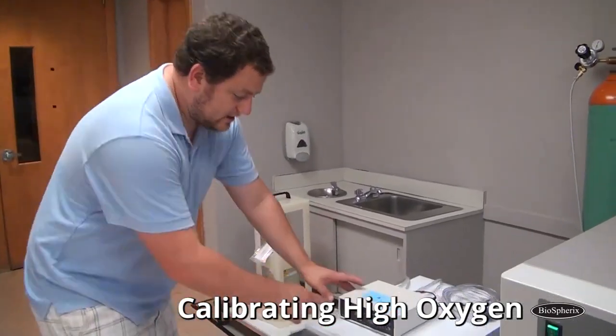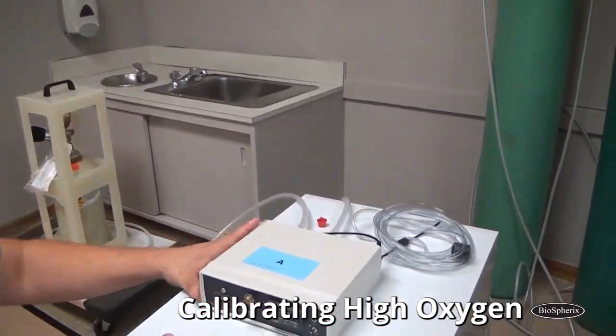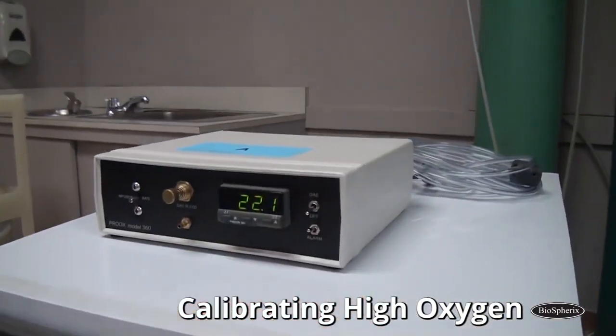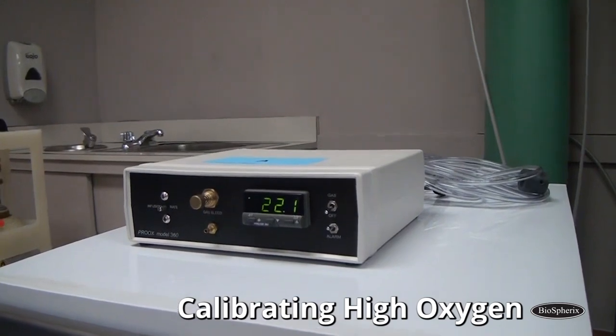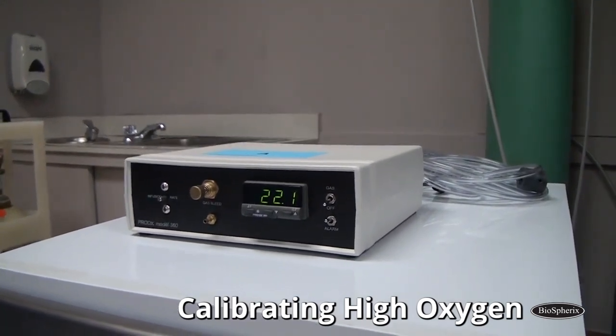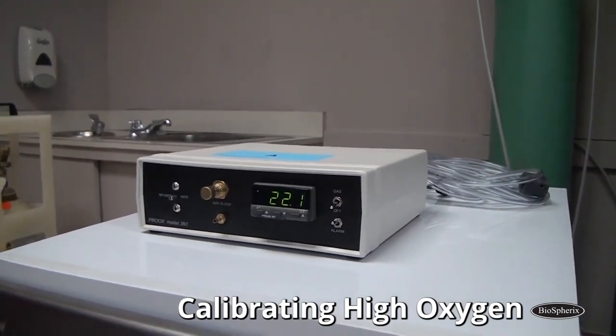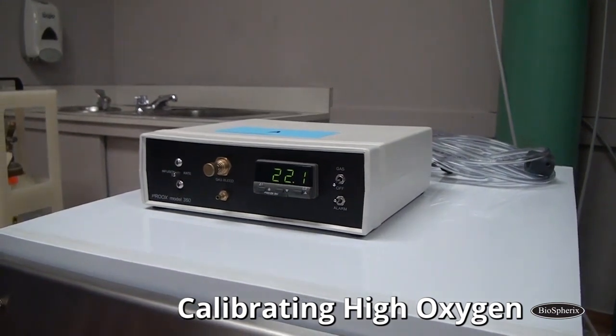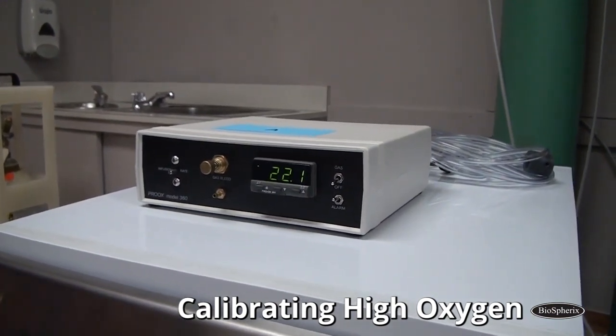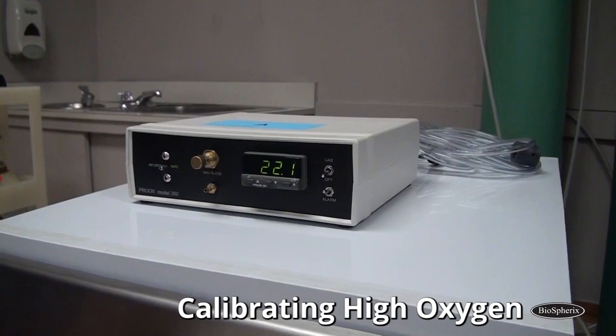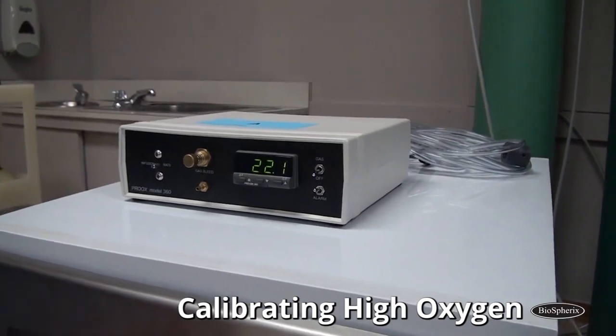So I'm going to go in, look at the controller, and I see it's reading 22.1. I know I need to make a calibration change because it's reading off from where it should be. It's probably drifted. It's been a couple weeks since I did my calibration. These sensors drift just like normal. I'm going to do it.